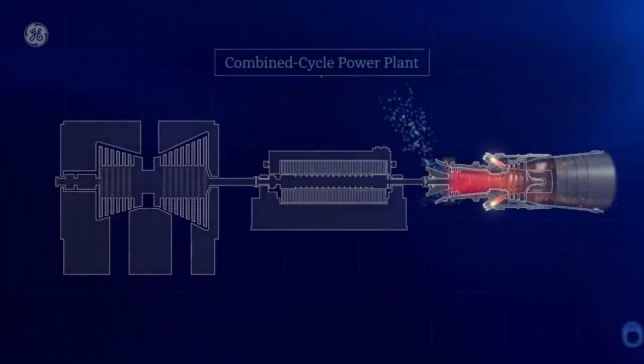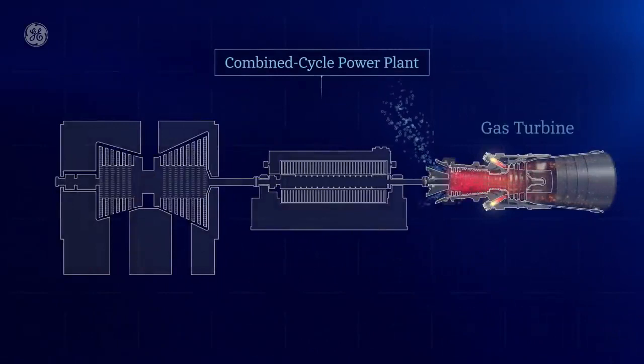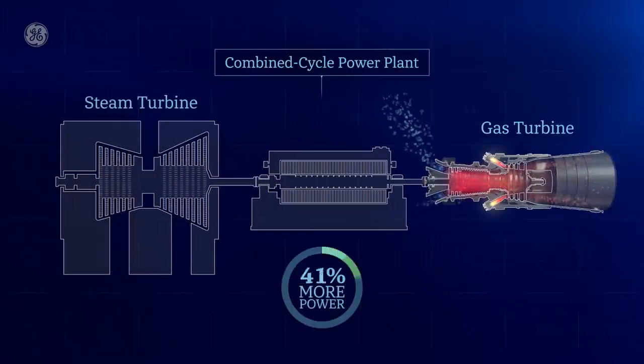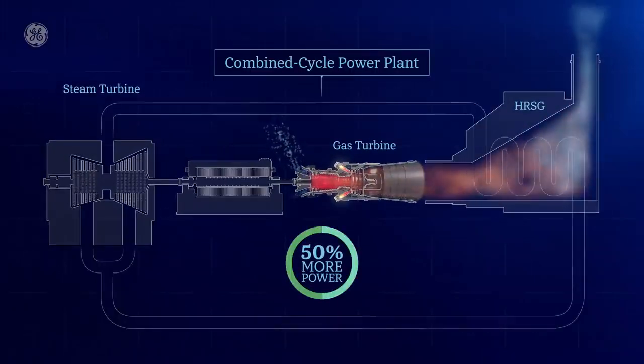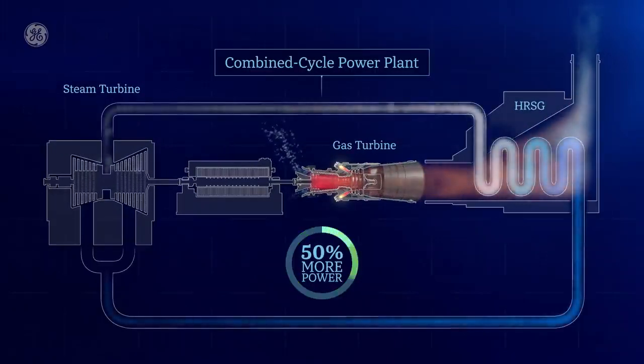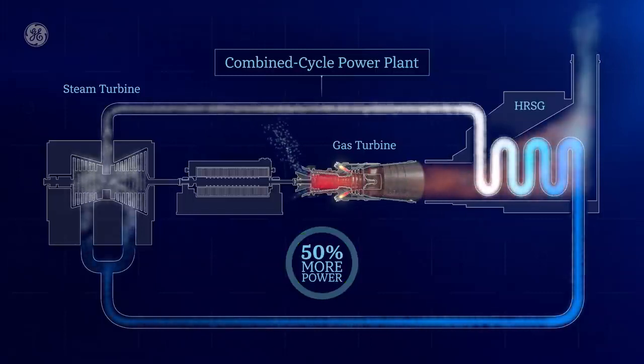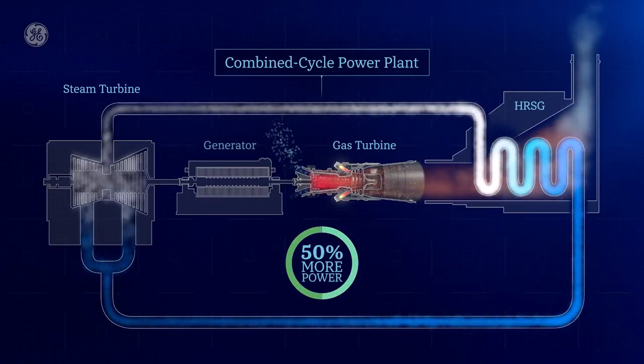In what's called a combined cycle power plant, the gas turbine can be used in combination with a steam turbine to generate 50% more power. The hot exhaust generated from the gas turbine is used to create steam in a boiler, which then spins the steam turbine blades with their own drive shaft that turns the generator.